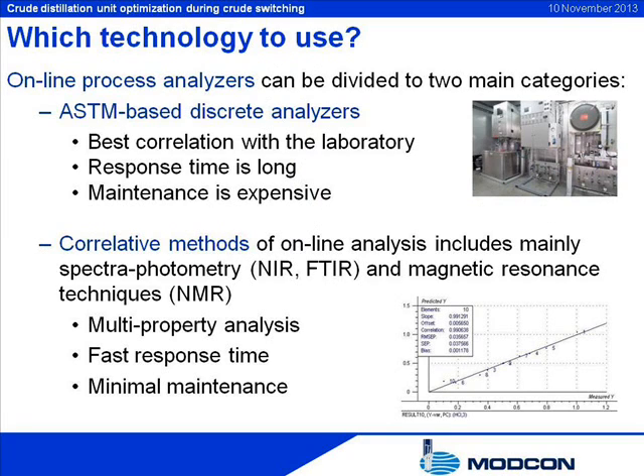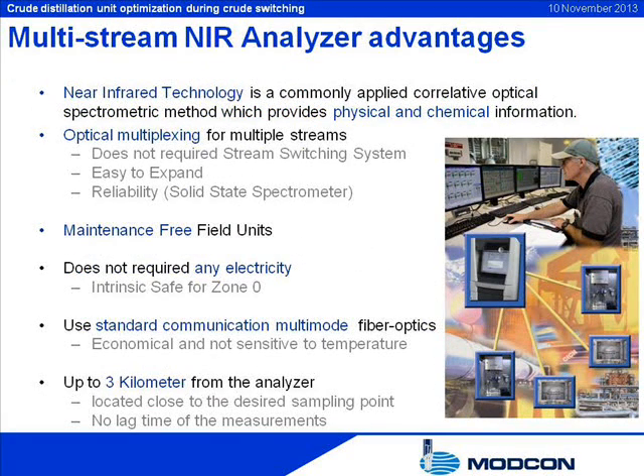Many dedicated ASTM-based analyzers are required to achieve this goal; however, their cost of installation and maintenance is high. Spectrometry-based correlative analyzers are able to perform simultaneous multiple measurements of a variety of physical properties. NIR analyzers are usually simple to install, very reliable, and require minimum maintenance. However, this technique is not linear and not all components in the sample are clearly resolved, so any changes in stream composition or process conditions require the model to be updated.